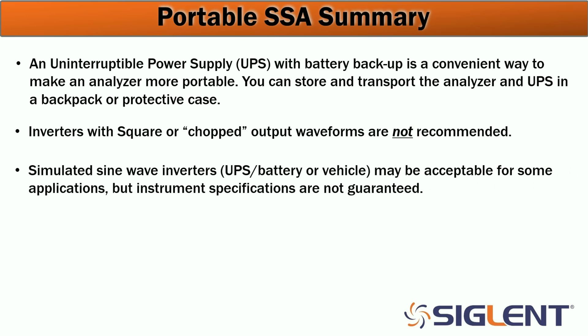And so to summarize the remote powered SSA application: An uninterruptible power supply with battery backup is convenient and usable. Stay away from chopped waveforms or chopped outputs. Simulated sine wave is acceptable but a true sine wave is going to be better. And to ensure accuracy we recommend comparing data from mains powered measurements along with data collected in your remote or portable power application. The more data you collect and the more comparisons you get, the more comfortable you're going to be with the data that you have.